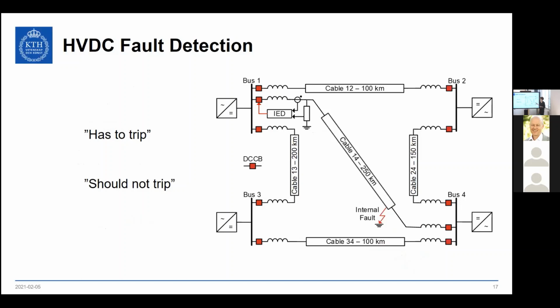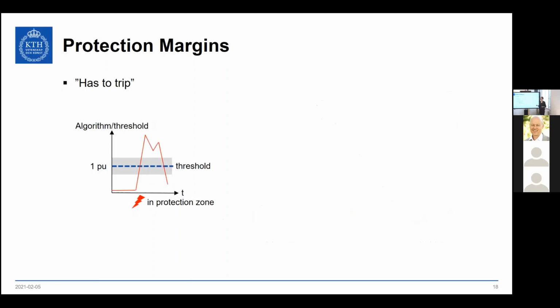One more high-level comment I want to give is the requirements on the protection in terms of reliability. And again, if we have a fault here, you have to have certain positions in the grid that's on this protection zone, and not shown down here, they have to trip. So those responsible for that protection zone have to trip, and then every other position in the grid should not trip. And if I keep these very simple terms, have to trip or should not trip, and translate it back into the actual fault detection algorithm, it looks approximately like this.